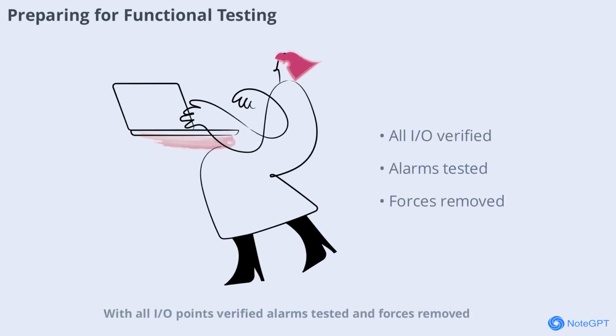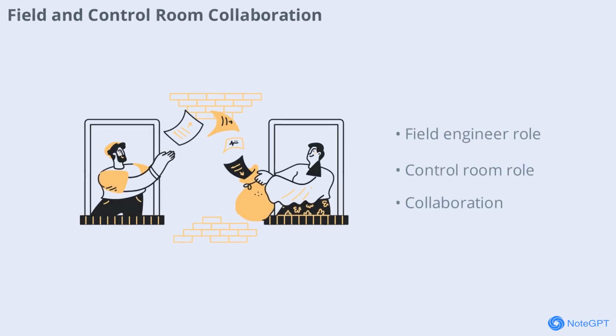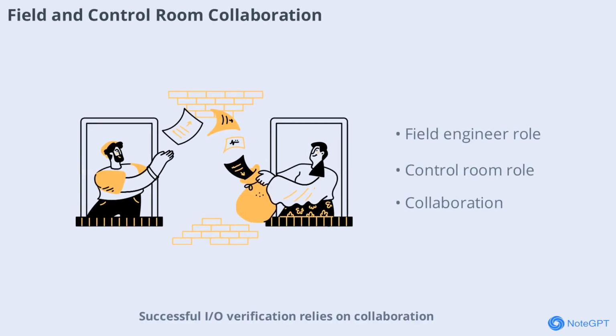With all I/O points verified, alarms tested, and forces removed, the system is ready for functional testing. This preparation ensures that the control system operates as designed and that any issues are addressed before live operation. Successful I/O verification relies on collaboration between field engineers and control room engineers. Clear communication and teamwork ensure that every device is tested and every signal is confirmed, supporting safe and efficient commissioning.